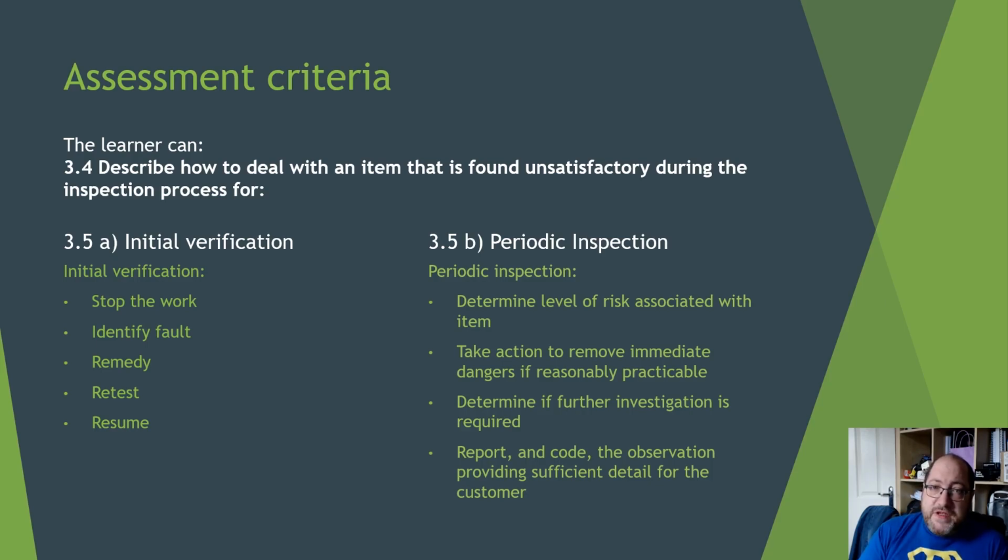We'll determine if further investigation is required and then report, coding it, doing the observations and recommendations with sufficient detail for the customer. So don't go "faulty socket", don't go "broken cable". Actually explain the problem, explain the cause, and explain the solution. Give the customer something to actually work with, think about, and cost. Okay.